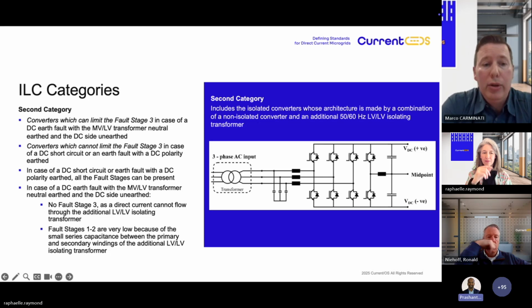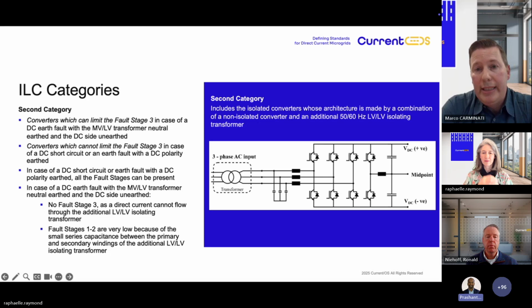In case of a DC earth fault with a medium voltage, low voltage transformer neutral earthed and the DC side, so both positive and negative, unearthed, we don't have the fault stage three. As you know, a direct current cannot flow through the additional low voltage isolating transformer windings. And also the fault stages one and two are very low because of the small, let's say, series capacitances between primary and secondary windings of the isolating transformer. I remind you that these are transient components. So theoretically, let's say they can pass through these very small series capacitances.